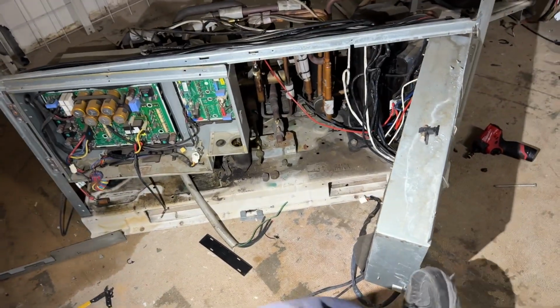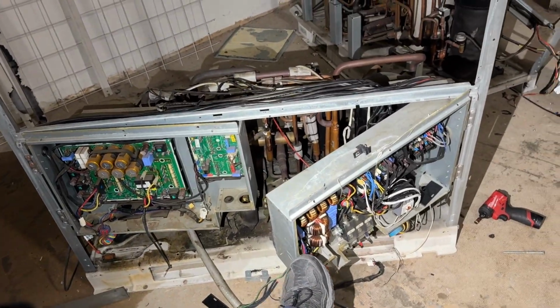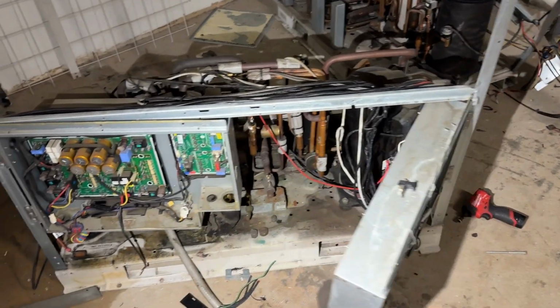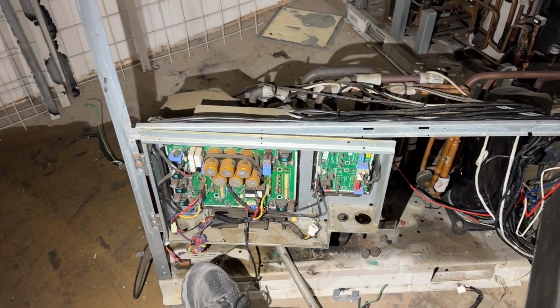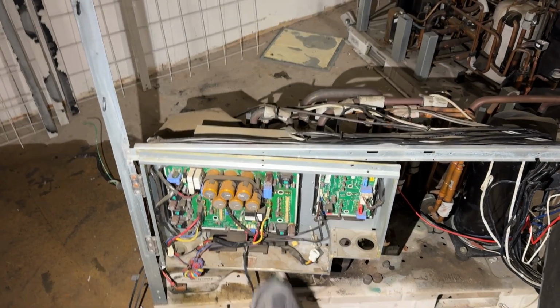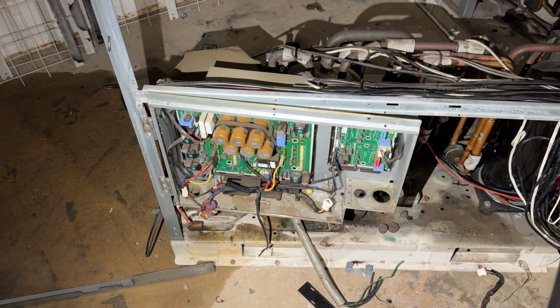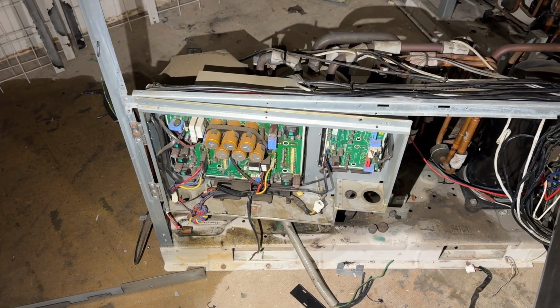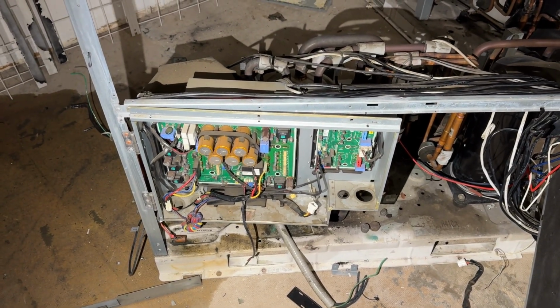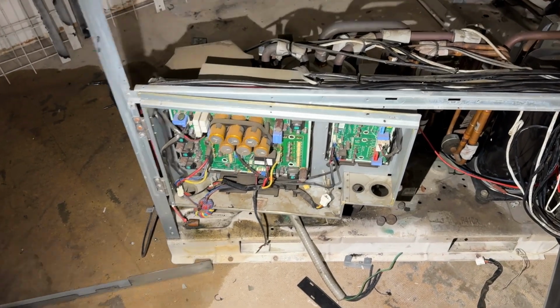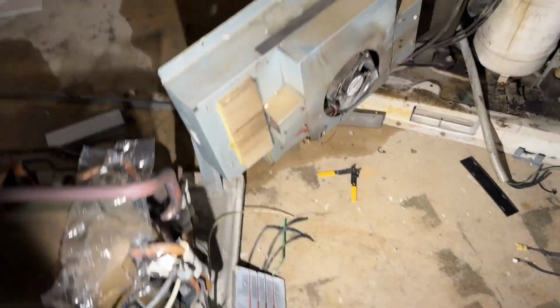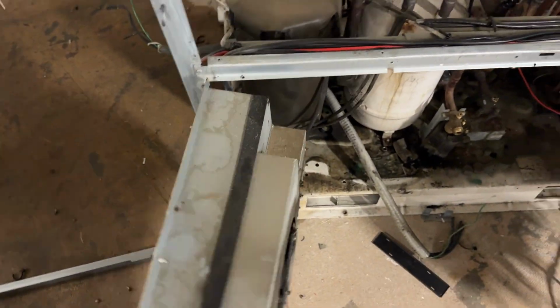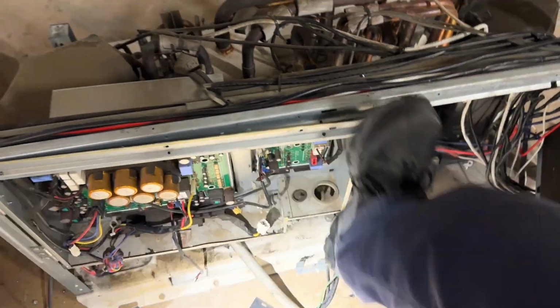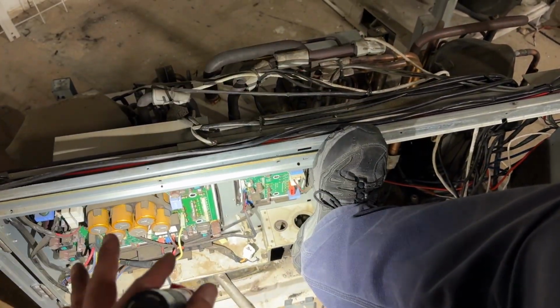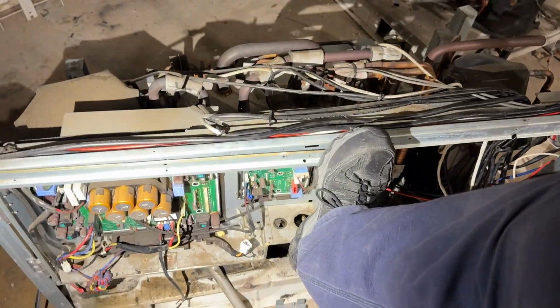Anyways, back to these reactors. You've got power coming out of the noise filter board, going through the reactors, and then this is the main power feed for the inverter board. So what that's most likely doing is not noise filtering, but since these are such beefy inductors, what it can do is smooth out any kind of choppiness in the current flowing through this board as it's modulating and doing all that weird crap it does.